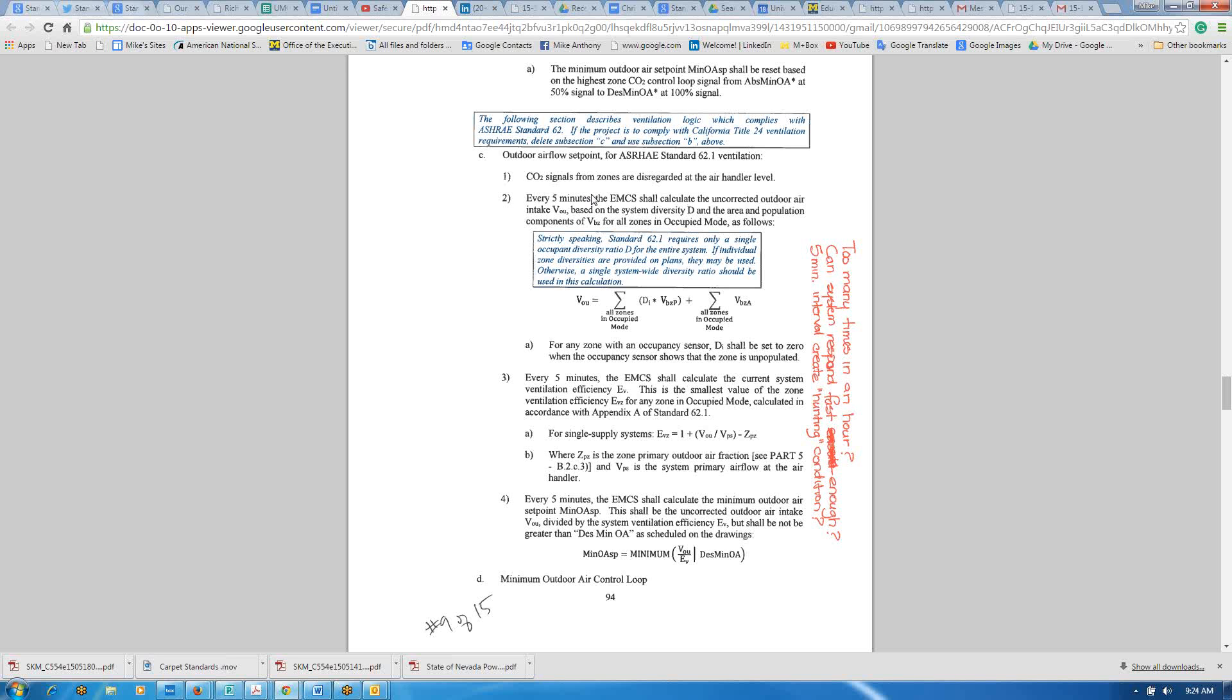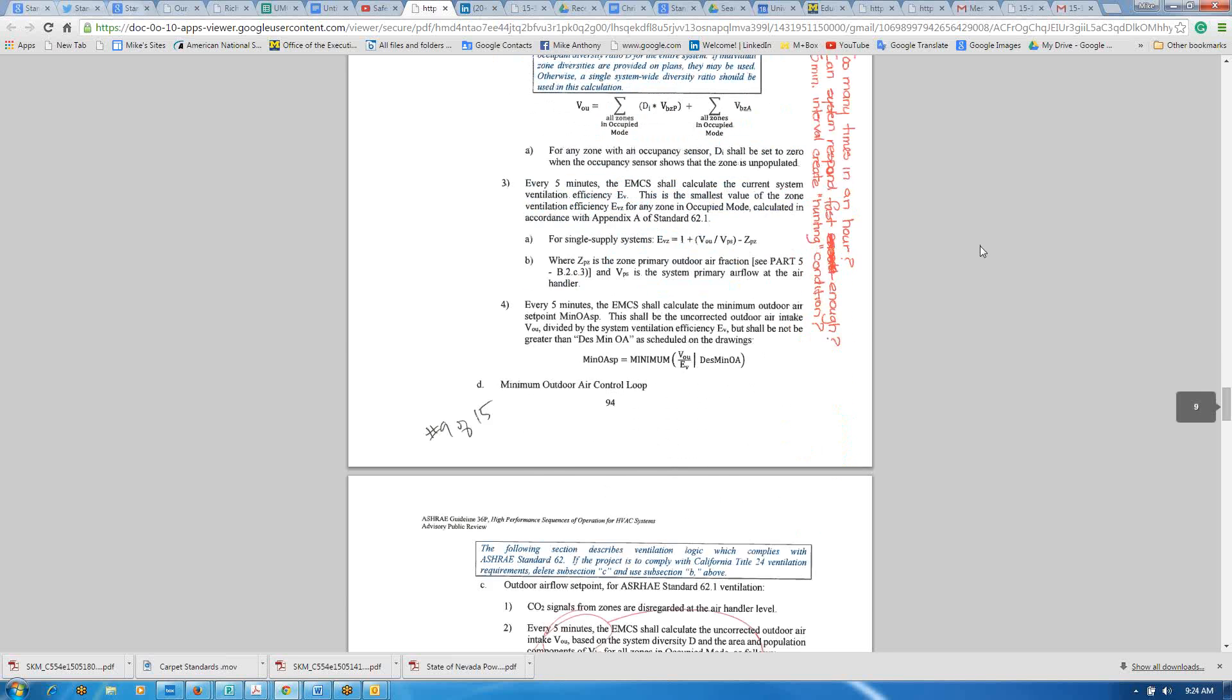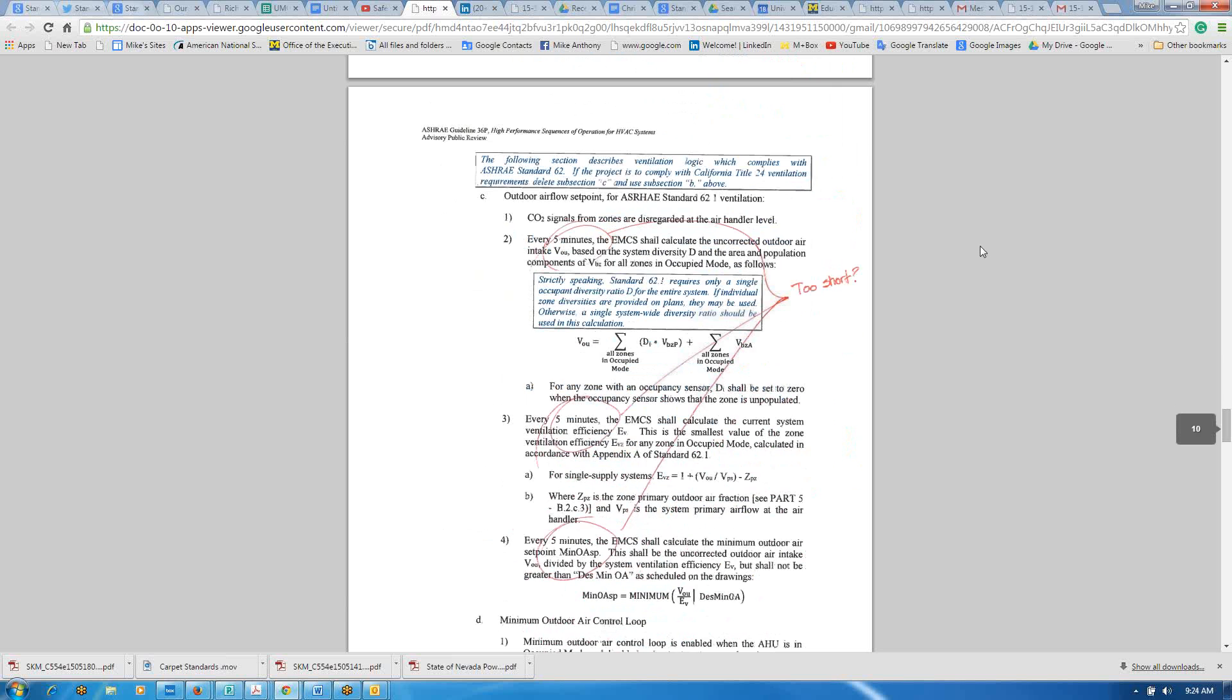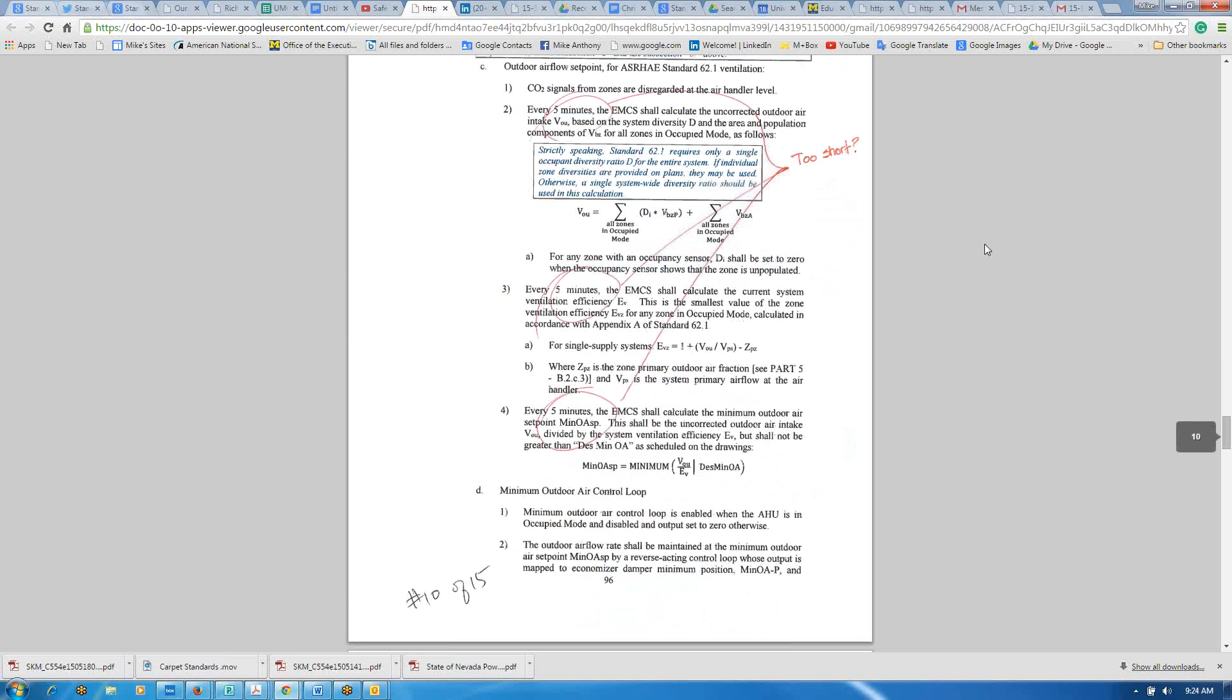That gets into the data flow issue too, depending on how fast the networks are. In new systems they may be different than from legacy systems, so I agree that prescribing five minutes may not be the best time. It needs to be optimized based on data throughput or the system capability. And the stroke time for dampers and valves. If it takes a minute for a damper to complete its stroke, and then another minute for a valve or something else, and then another couple minutes for the condition to adjust in the space, I just felt five minutes you're going to be doing a lot of hunting. The dampers are going to be in constant motion in the valves. It strikes me that four times an hour is sufficient. I thought five minutes was too soon, but honestly, I can't tell you what is the best time. What consideration do we make for fire compartmentalization? Very often there are duct detectors in these systems. There could be on air handling smoke detectors, CO2 sensors, stuff like that. Next page, I said the same thing.